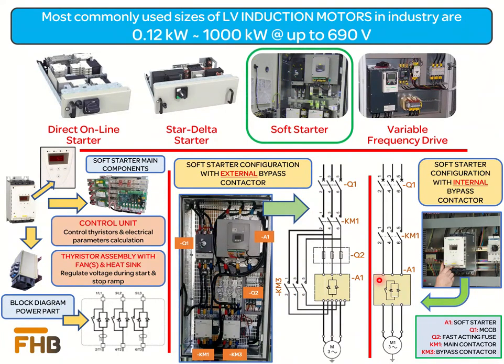Other power components involved in the soft starter circuit are the external short circuit protection device and the main power contactor to control the motor start and stop. Fast acting fuses are added in the circuit to achieve type 2 coordination.